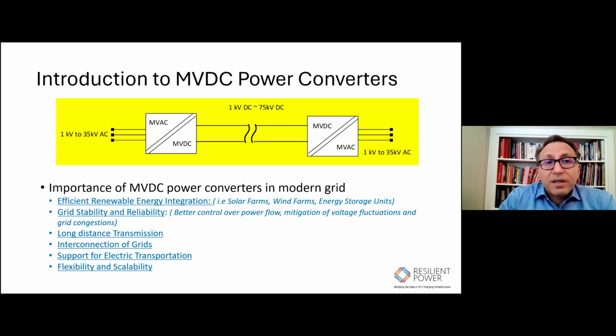They also have an impact on grid stability and reliability. MVDC has much better and easier power flow control. There is no oscillation created by capacitor switching. When we do capacitor switching, there could be some voltage oscillation that can peak up to 2 times the voltage. There could also be some resonance in AC transmission, because of the inductance or capacitance of the power line or the passive filters of the inverter-based generators. Those are eliminated when we have DC power flow.